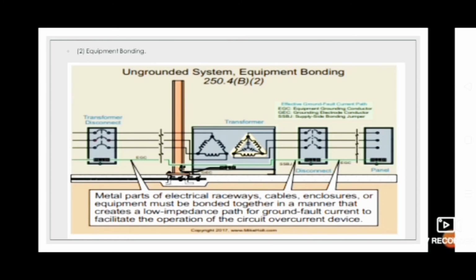This is equipment bonding. Metal parts of a raceway, cable, enclosure or equipment must be bonded together in a manner that creates a low impedance path for ground fault current to facilitate the operation of the circuit overcurrent protection device. The fault current path must be capable of safely carrying the maximum ground fault current likely to be imposed on it from any point of the wiring system should a ground fault occur to the electrical supply source.